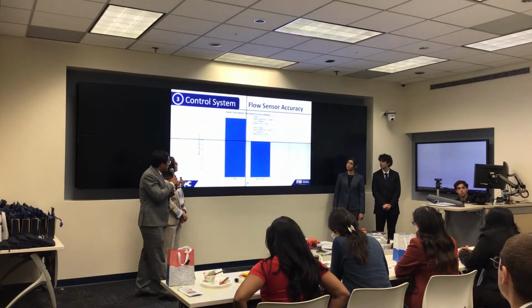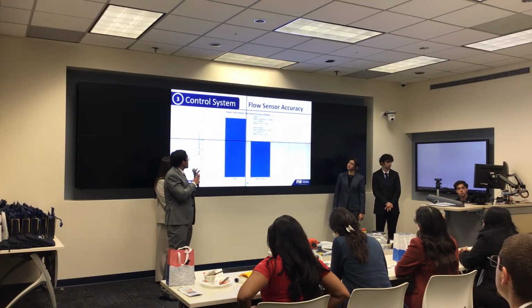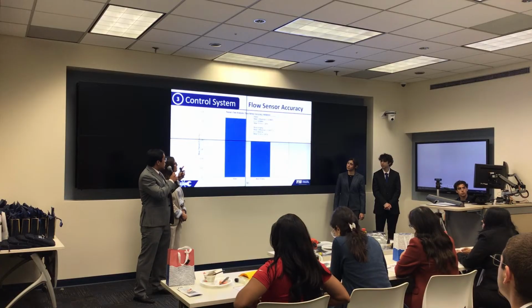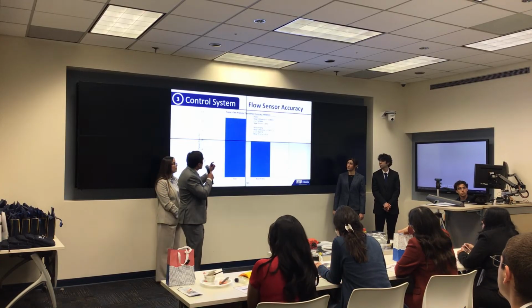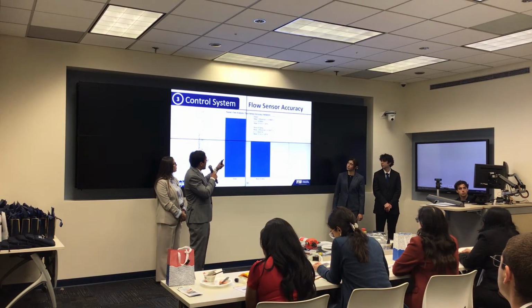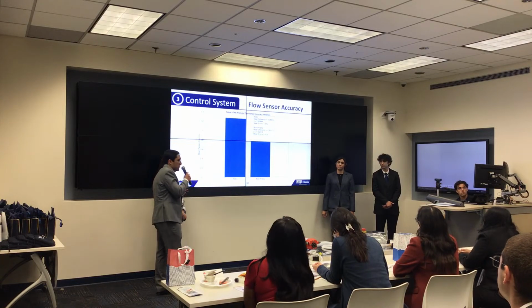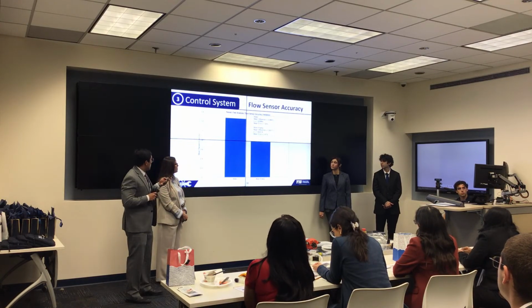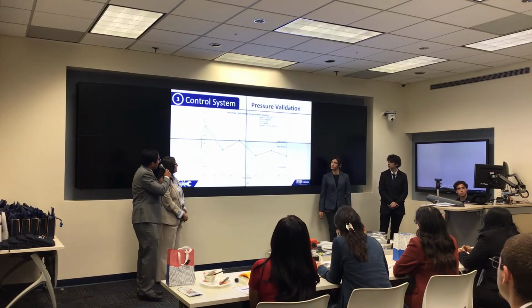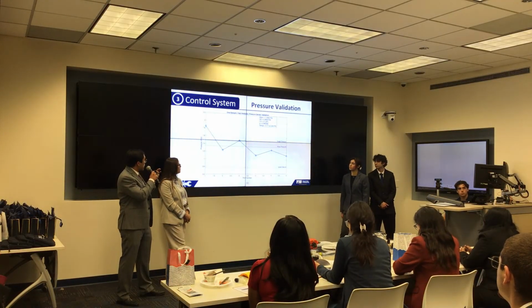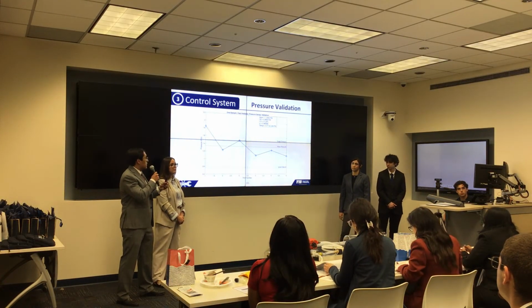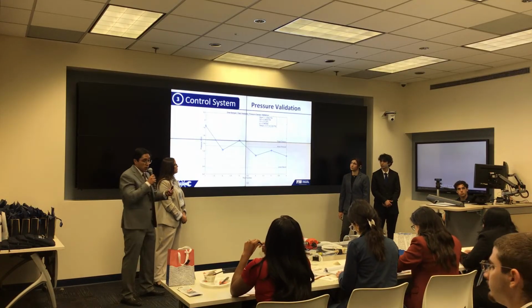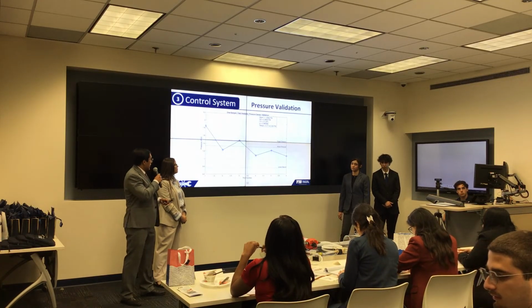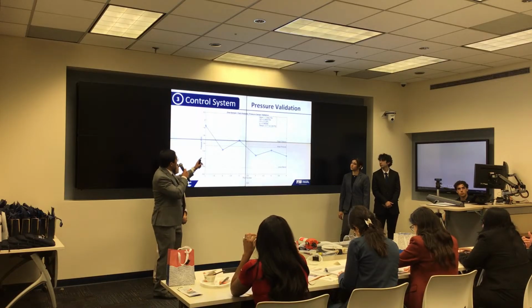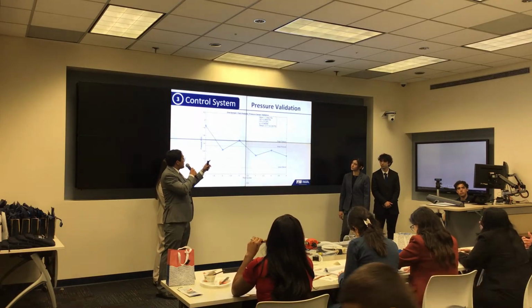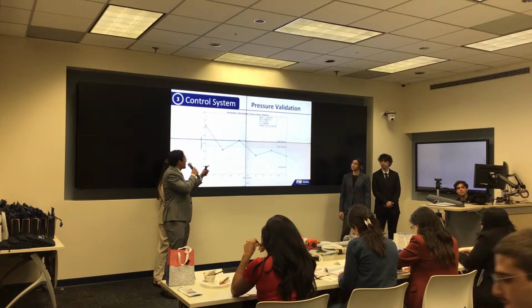Next, for flow accuracy, we compared the flow sensor readings to collected volume. And as we can see, the error for water and blood analog is very small, showing the accuracy of our flow sensors. Lastly here, we show different values of pressure that we adjusted with our needle valves. And as we can see, these values fall within the range that we need of 0.77 and 2.20 psi.